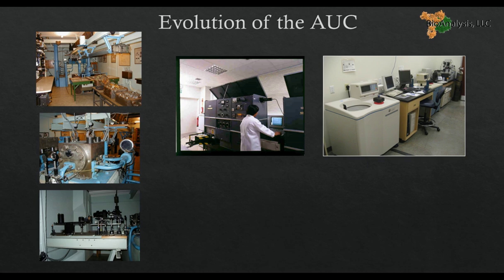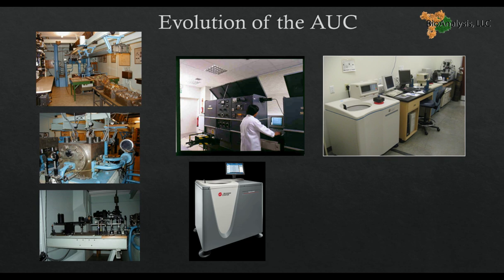Recently, Beckman has pushed out the new Optima AUC, which improves upon the XLA and XLI with improved scanning frequency, better optical systems, faster collection rates, and better cooling systems. This is pushing the boundaries again. With these modern softwares, you can now apply the theory and versatility of AUC to a wide variety of systems — not just biologics, but also nanoparticles and polymers. AUC is the gold standard in measuring size distributions, molecular weights, and hetero- and self-associations.